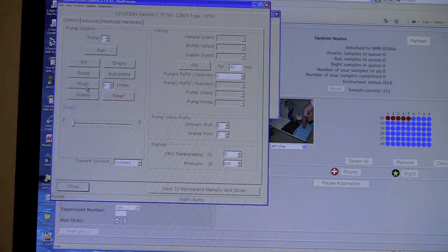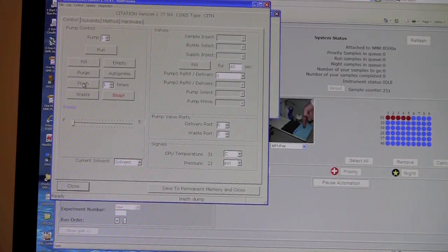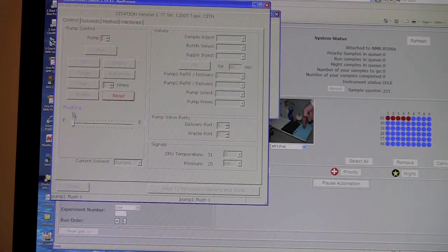So what we want to do is flush the syringe pump. This will cause the syringe pump to empty and then refill. Down here, this is a little graphical depiction of the syringe pump. So right now the syringe pump is full of solvent, and as we flush it, it will slowly move this way, dispensing the solvent into the probe. When it gets to the end, then it will refill from the solvent reservoir until it's full again. So I'm going to press flush, and we can see now that it's flushing, and it will empty out. Now it takes quite a while for this to happen, so I am going to wait for it to happen and come back after it's finished.